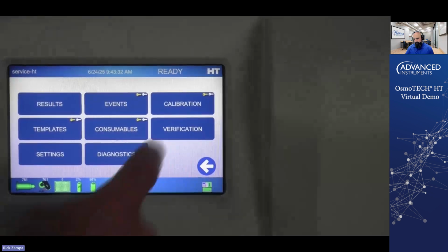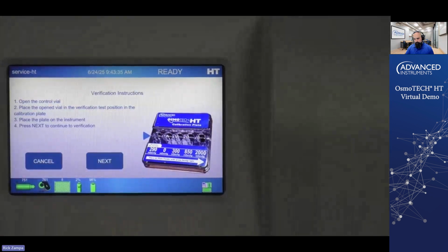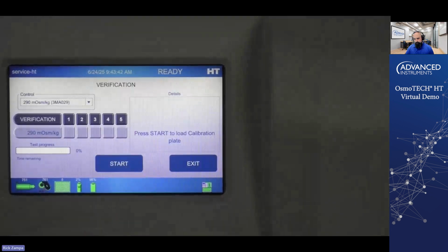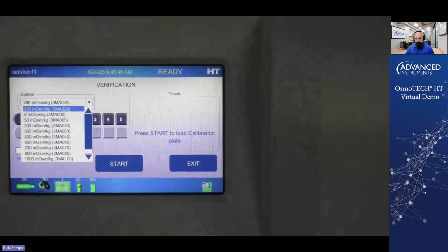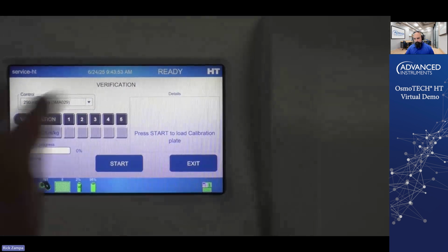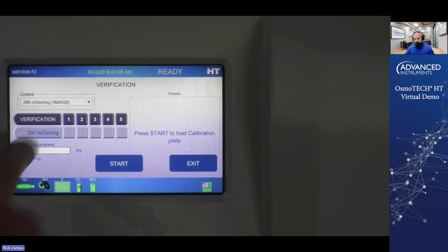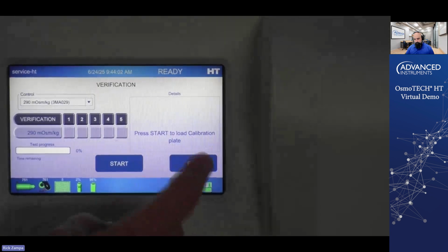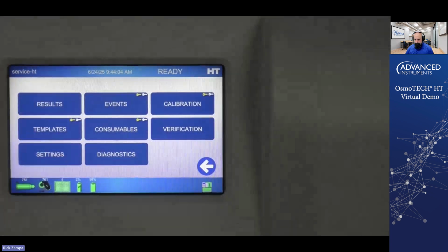You can also run just a verification using the same plate. You would put just one ampule in here, and when you get to the verification point, you would hit next, and then you can choose which verification standard you want to use in the next section. Any of the many calibration standards that we have available you can use. In this particular case, we have it set up for the 290 reference solution. It would run 5 replicates and then give you the statistics on that verification. I'm going to exit out of that. So that's calibration and verification.